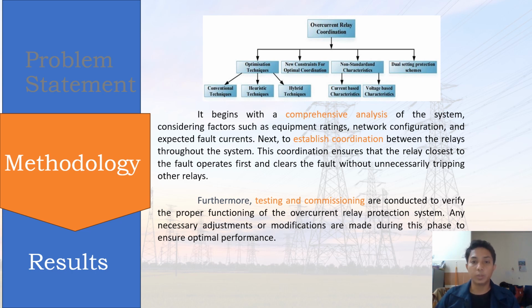scheme. It begins with a comprehensive analysis of the system, considering factors such as equipment rating, network configuration, and expected fault current. Next, to establish coordination between the relays throughout the system. This coordination ensures that the relay closer to a fault operates first and clears the fault without unnecessary tripping of the other relays. Furthermore, testing and commissioning are conducted to verify the proper functioning of the overcurrent relay protection system. Any necessary adjustments or modifications are made during this phase to ensure optimal performance.